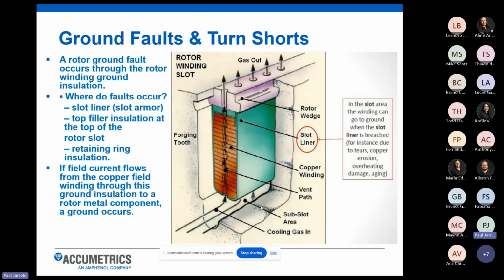So this is an example of what the field bus bars look like when they are installed inside of the generator rotor. There are grooves cut on the cylindrical generator rotor, and there are many different stack-ups of these field bus bars, or field windings, inside the rotor. Those are insulated from each other with thin pieces of insulation between each winding, but there's also a slot liner material, which is non-magnetic, that protects the current flowing through these copper bus bars from leaking over and causing a short to the rotor forging itself.